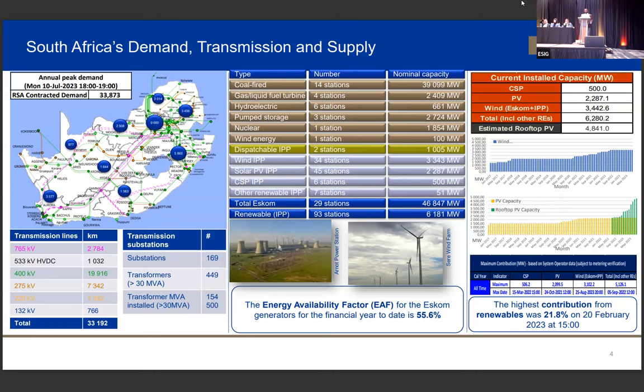Top right, total renewable 6.2, and then we've been trending the load. Since 2014, we've been gradually increasing wind, and in the middle, we've been gradually increasing the PV. But there's a lot of increase in rooftop PVs. Because of the performance of our fleet, customers are starting to put in their own rooftop PVs, and some are even going off the grid. Last year in March it was around 1,000 megawatts, and this year it's around 5,000, so about a 4,000 megawatt increase. Contribution from renewables this year was about 22%. So they're doing very well.